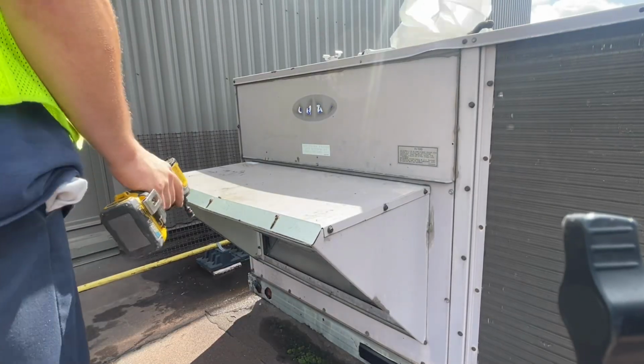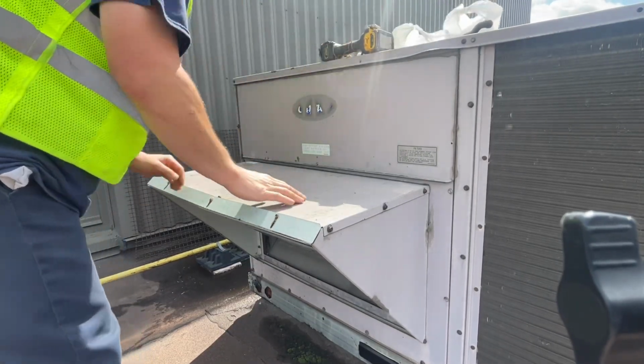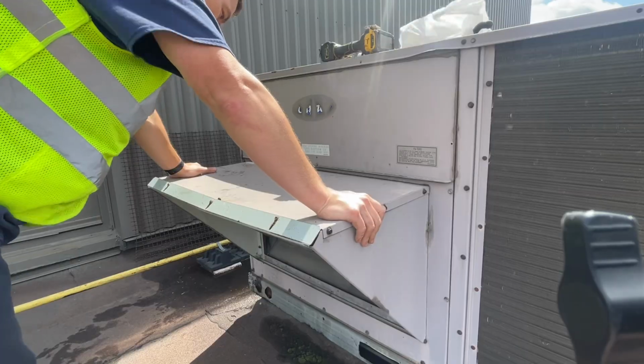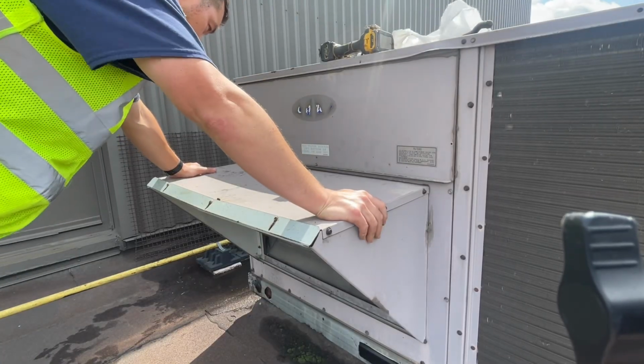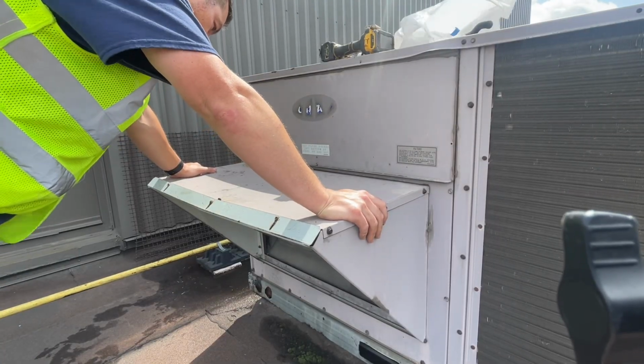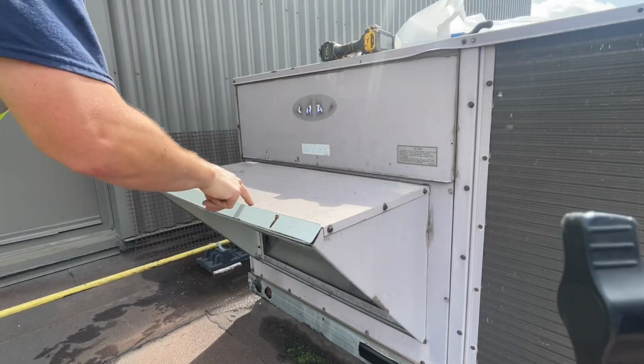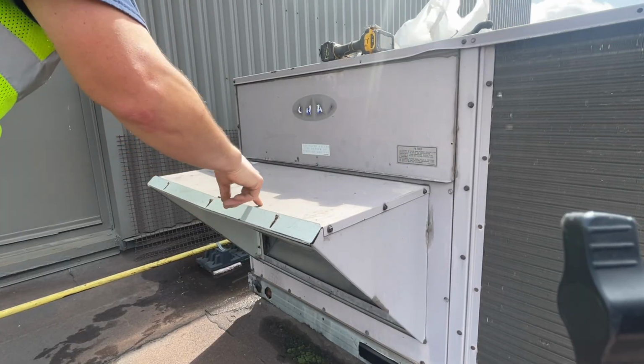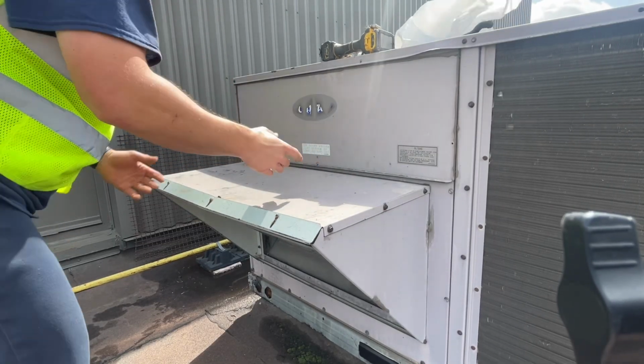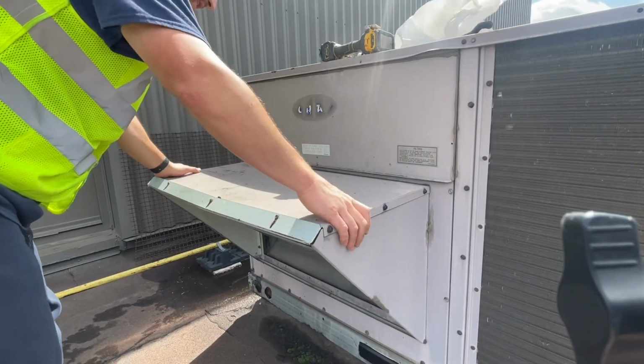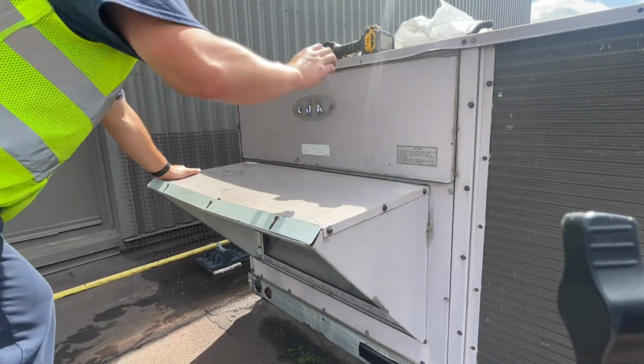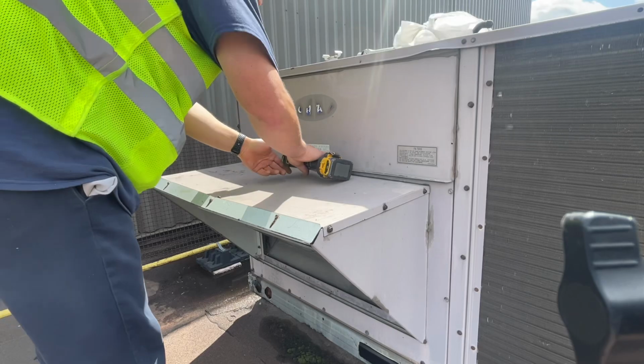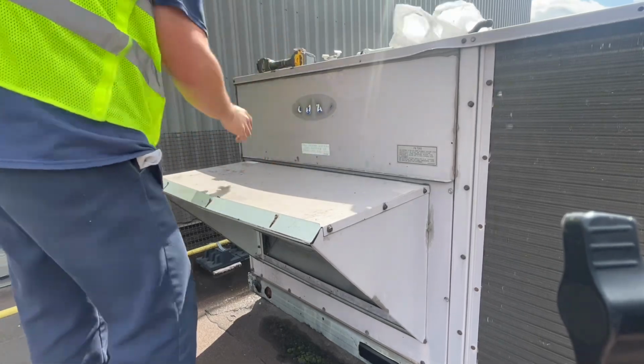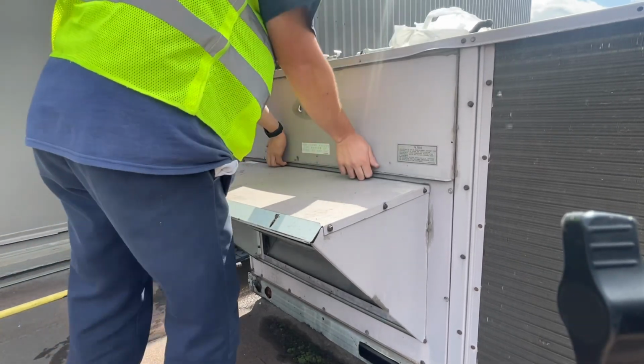And the final thing I'm looking for on this rooftop here is our economizer. So what this does is, when our ambient temperature is below 65 degrees, give or take, there's a damper inside here that will open, shutting off our compressors and therefore saving hydro for our customer. It just essentially provides free cooling. But if you guys are ever in doubt whether you have an economizer or not, they're always gonna be on your return side, so your filter door.